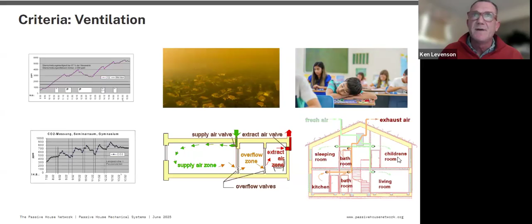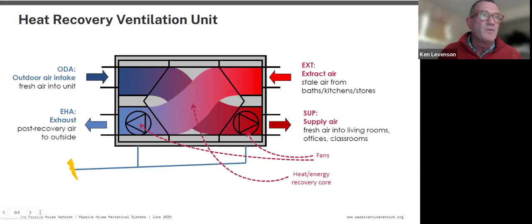A key aspect is how this air will move through the space, whether part of a bigger building or a single family home. For the units, we have on the exterior of the building the outdoor intake, fresh air coming in, going through the heat recovery core and being supplied as conditioned air. There are two fans, one on the supply side and one on the exhaust side, and there are filters, one on each side as well.